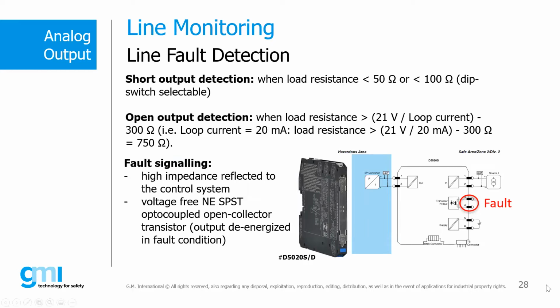Yes. And also in the case of the analog output, let's see how a line and/or load fault is managed. In this case, it's the barrier itself, in addition to limiting the current and voltage toward the field to non-dangerous levels, that carries out a real diagnosis of the loop towards the hazardous area. In fact, the internal circuit of the barrier is designed to provide us with a real fault signal when very precise thresholds are exceeded. In the case of the GMI device in the slide, it is able to detect a short circuit fault when the impedance of the load and the line falls below 50 ohms or 100 ohms.